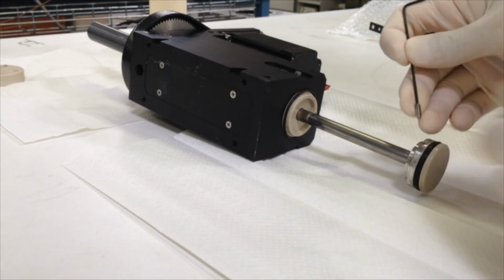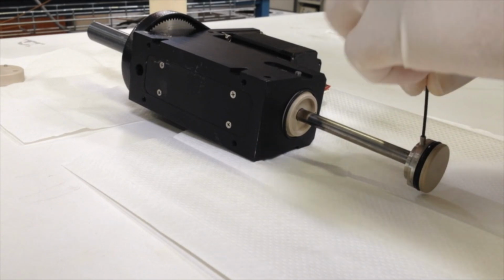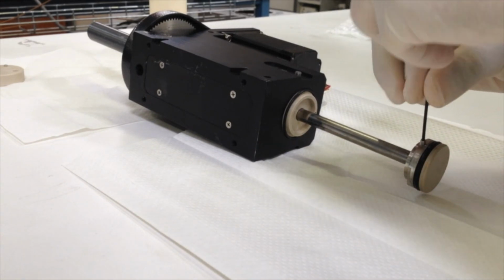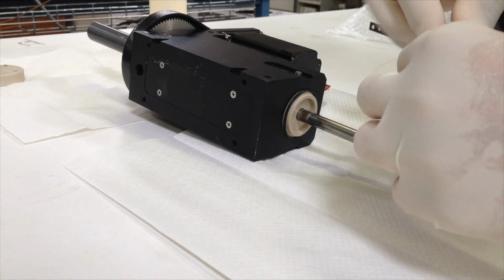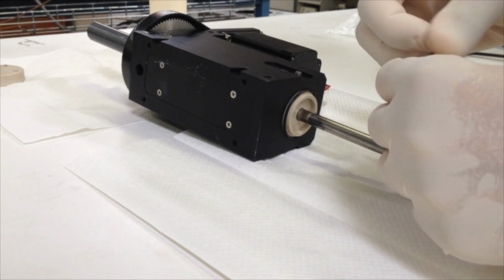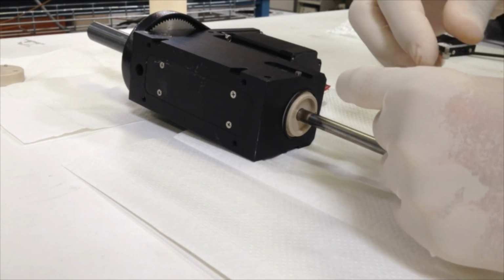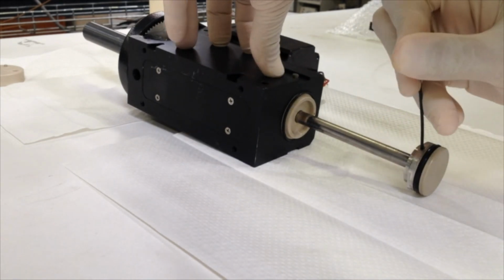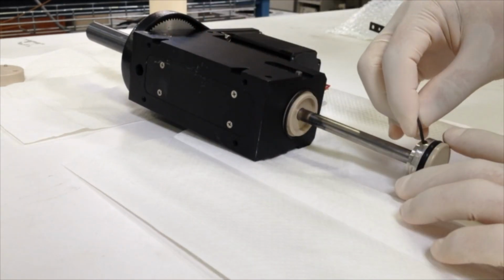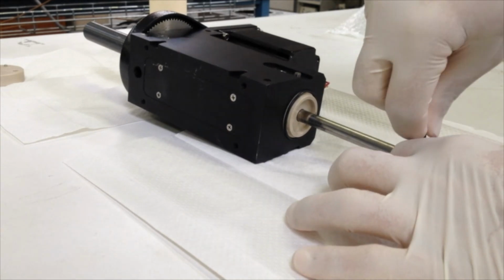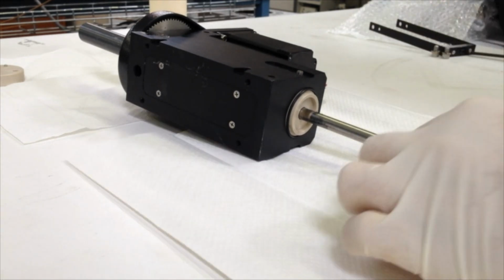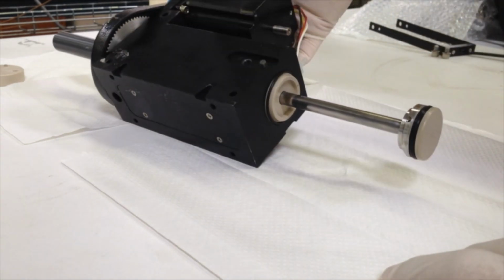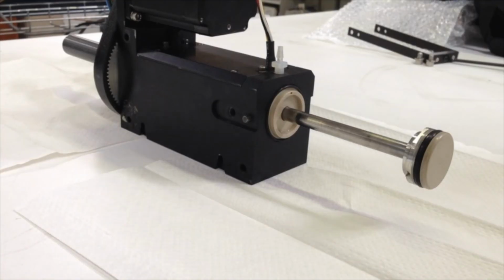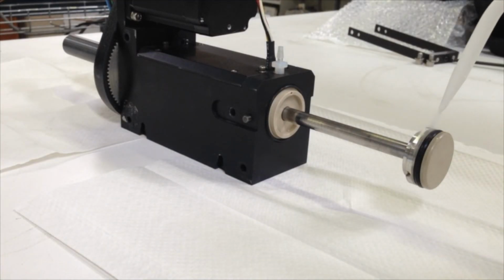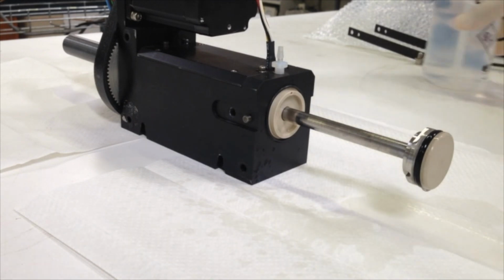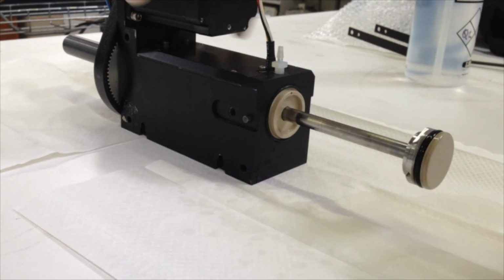Next, screw in a new brass-tipped set screw into the piston head. Make this very tight. The brass tip will form to the threads of the lead screw. Never reuse the brass-tipped set screw. Lubricate the piston head with methanol and then push the ceramic cylinder back onto the pump body while turning in a clockwise motion.